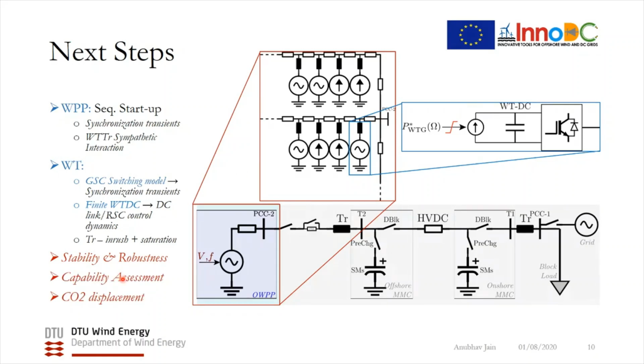Some long-term studies include capability assessment. This means system level studies to see how the wind variability affects the black start service or the voltage stability at the onshore PCC. And also an interesting study to do is the CO2 displacement, to analyze the CO2 displacement by these grid forming wind turbines, as they would replace, or at least minimize, the use of the diesel generator on the offshore substation, and this would ultimately translate into cost benefits.